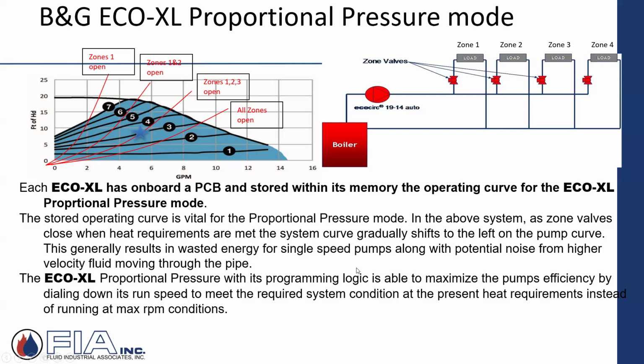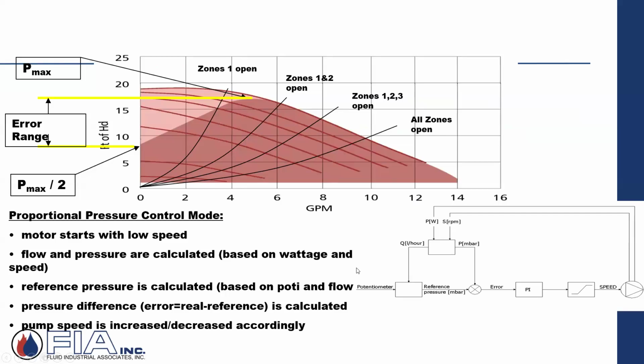What I'm going to do is reduce your speed. I'm going to reduce that electronically pulsing to reduce the RPMs, which reduces the kW, and I'm going to fall back down on this proportional curve. And as more zones close, I continue backing down that curve. That's all it's doing. So during the course of the heating season, times how many heating seasons, this logic is just constantly changing, opening and closing valves, speeding up, slowing down, all the while reducing energy consumption as effectively as possible. So it's a very popular light commercial application. I don't need to get into that.